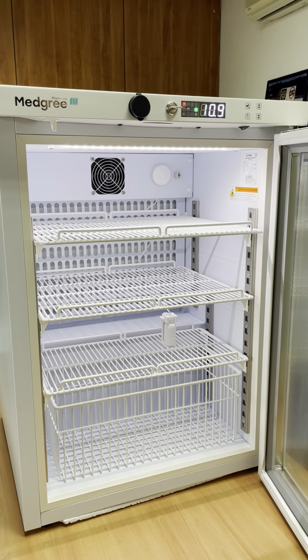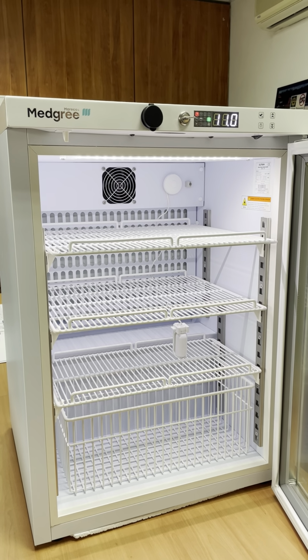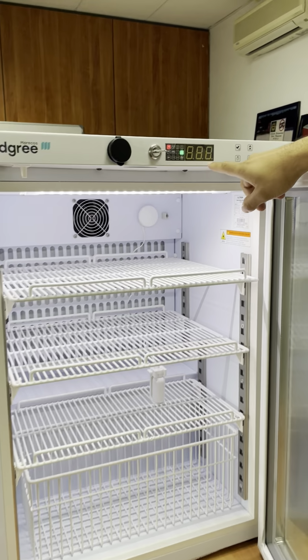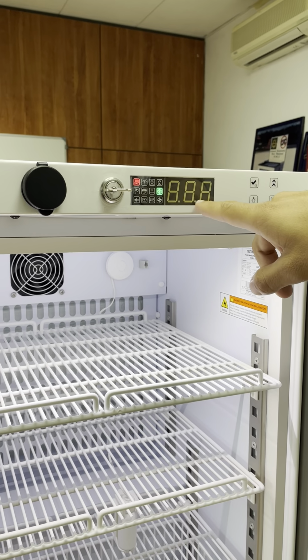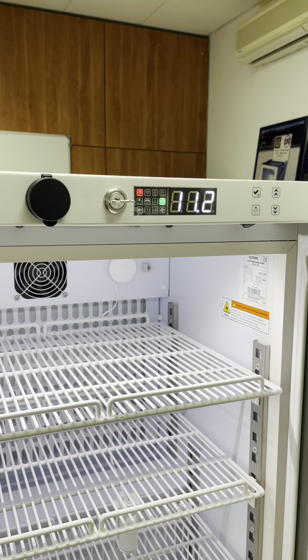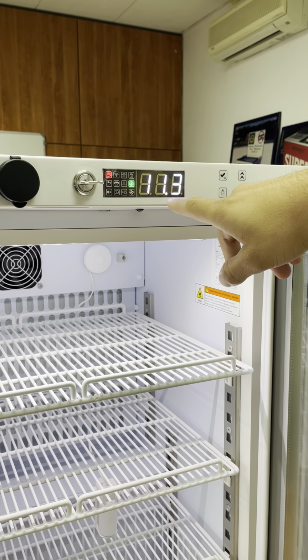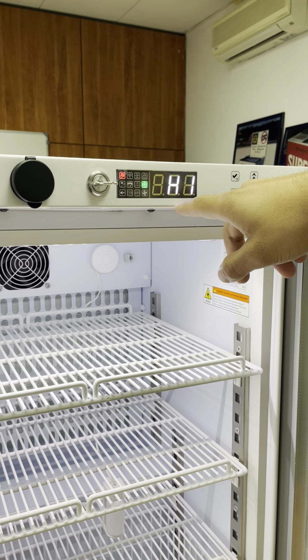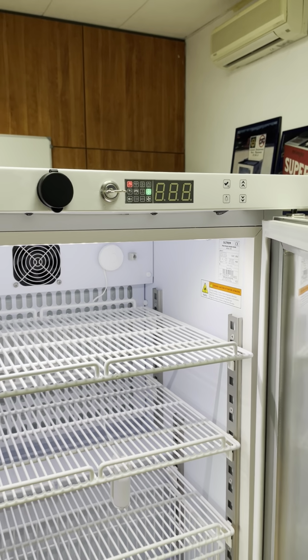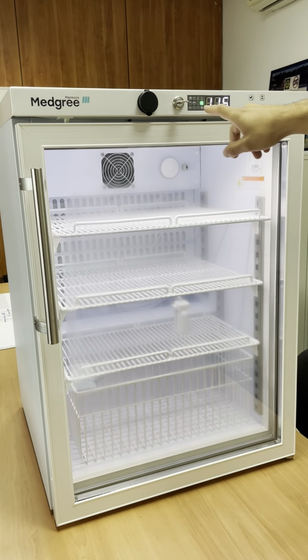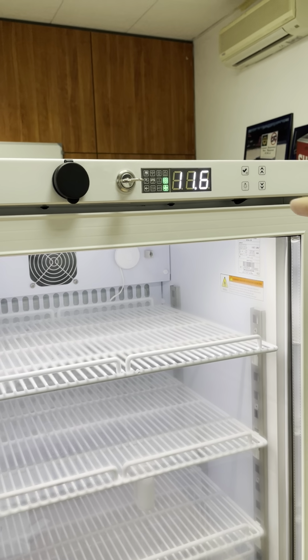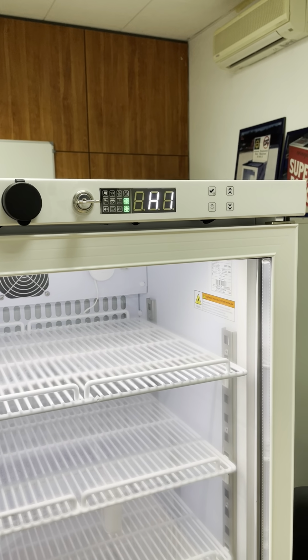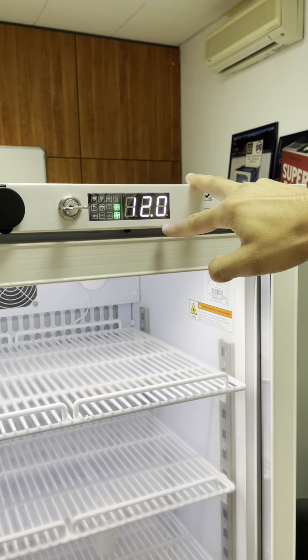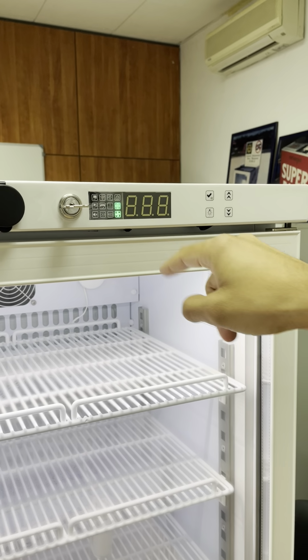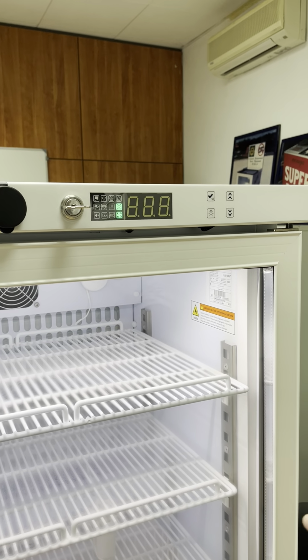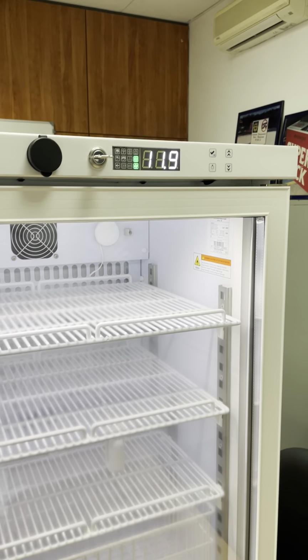I'll just keep it open for some time so we can hear the alarm. So we already have the high temperature alarm. H1 means high temperature, and you have DO meaning door, so open door. We are having two alarms at the same time. High temperature because of course the temperature alarm is defined at 8 degrees, and when it is above 8 you have the alarm. I will close it. So the door alarm already stopped, but we keep having the high temperature alarm. The high temperature alarm will stay as H1 until the temperature of probe 1 goes below 8 degrees. So we need to wait a little bit so it goes below 8 degrees again.